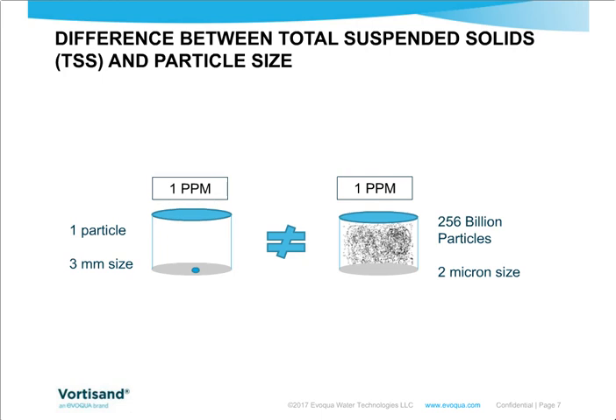Dispersants in some applications are used to break up particles and keep them in suspension so they're able to be filtered out. But when you use a dispersant, you're converting that small chip scale, or whatever that may be from your cooling tower or process, into small particles, much more difficult to remove with a filtration device.